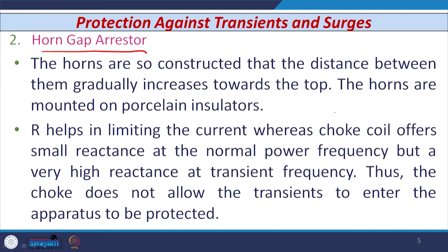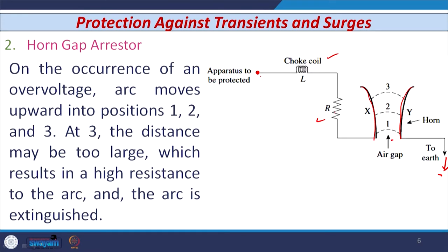The choke coil does not allow transients to enter the apparatus to be protected. On the occurrence of an overvoltage, the arc moves upward from point 1 to point 2 to point 3. When it reaches point 3, the distance is very large, resulting in high arc resistance. The arc lengthens and since R = ρL/A, as the length increases, the resistance of the arc increases, and the possibility of sustaining the arc reduces — the arc can be easily extinguished.